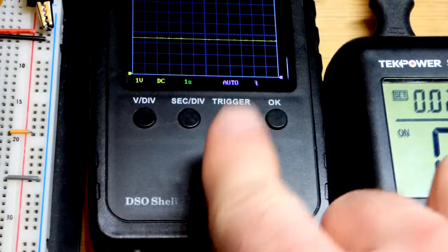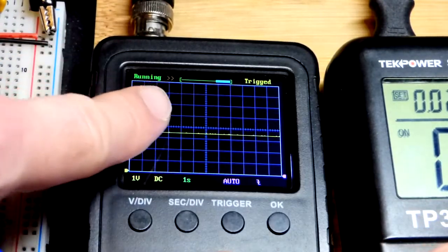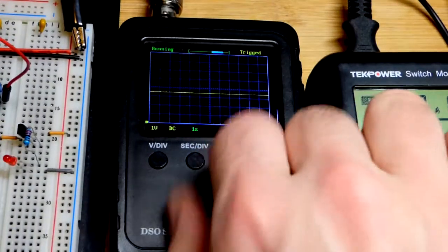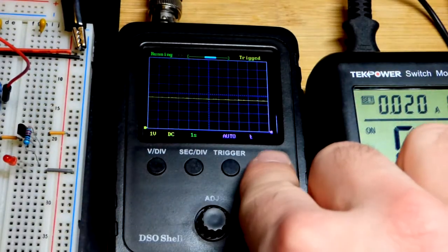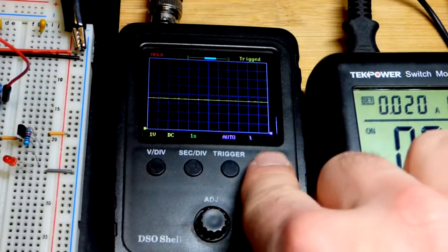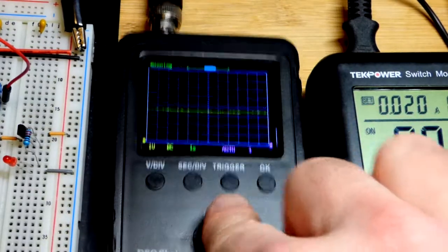If you press the dial straight down, right up there you'll see some arrows. So when you want to speed up what turning the dial does, you press that arrow. So now I have to turn this clockwise. I can zoom back a little bit. I have to turn this clockwise, but now that bar is moving towards the middle. And we can keep going. So what that's doing is we can pause this and then turn the dial to look back in time without it scrolling. Or we can go back in time while it is scrolling, whatever you want.